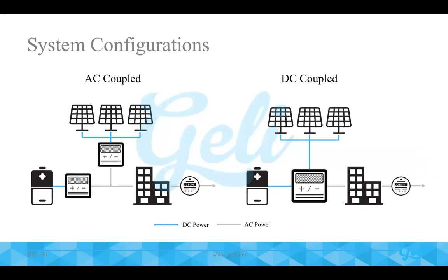The reason for this is that typically the solar array is much larger than the battery, and you'd need a really, really large power converter, and the system layout wouldn't be feasible because the solar array is on top of the building while the battery is typically in the basement or outside. That causes some headaches around making sure you're only charging from solar when you're ITC compliant.